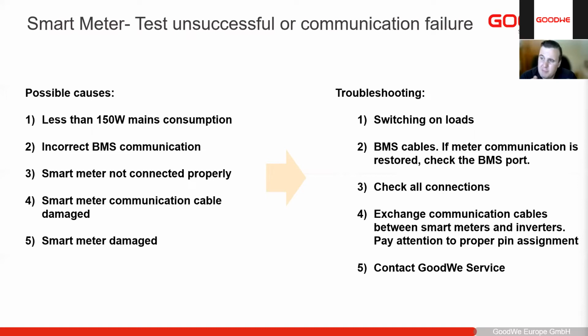If we do have any BMS communication errors or issues like that, if we don't have batteries, we need to make sure we set it to the no battery option so that the meter test will then ignore that BMS. So if the smart meter is not connected properly, it will also definitely fail.